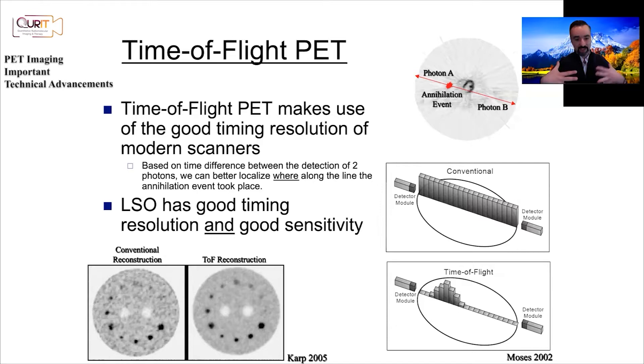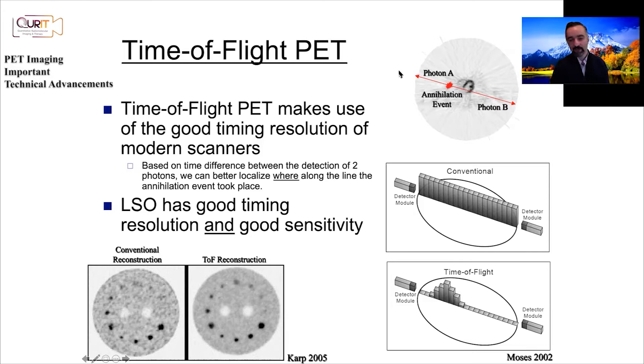Time-of-flight PET actually happened even before the major new push towards it. But some of those early scintillators were not very sensitive, so people set them aside and moved towards BGO. BGO doesn't have the timing characteristics that allow time-of-flight PET, but LSO does.